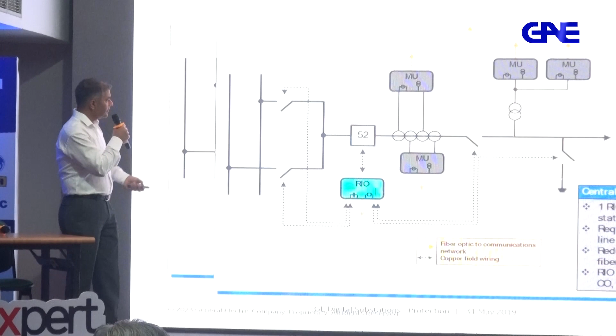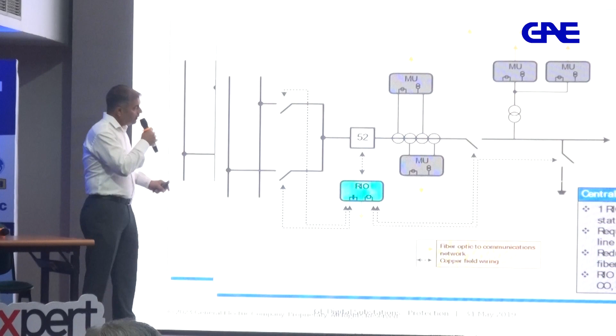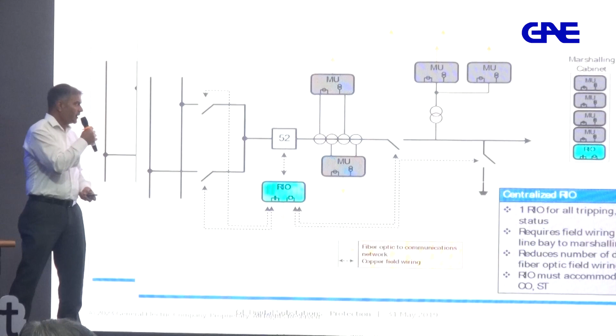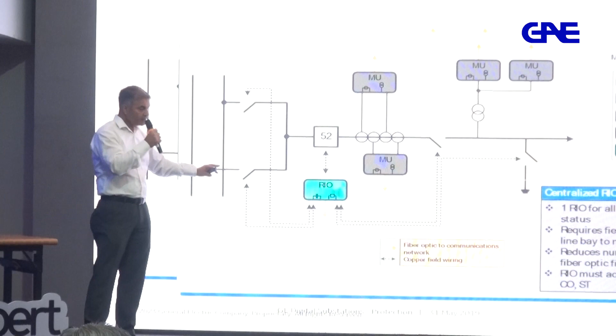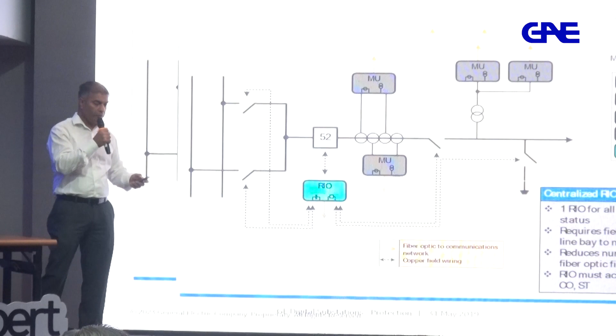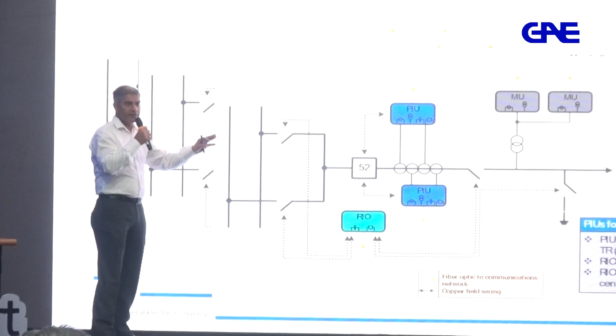Another option is that you use the centralized remote input output unit, centralized RIO, which manages all the trippings, status acquisition for all disconnectors and circuit breakers in a bay, okay? And you use a merging unit for CT and VT. This is another alternative. In this alternative, you have copper wiring in the field from your primary device up to the marshalling kiosk, but the rest of the things are all fiber optic. The third alternative is that you use the process interface unit. So that's PIU. And PIU is CTs, VTs, status, control, tripping, everything in one device, right? So you can use PIU or in conjunction with remote input output.